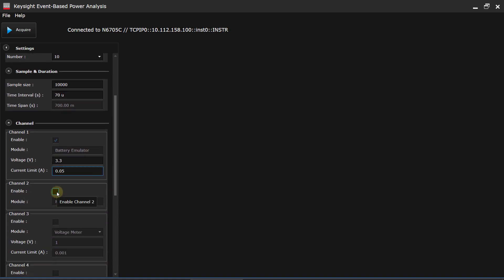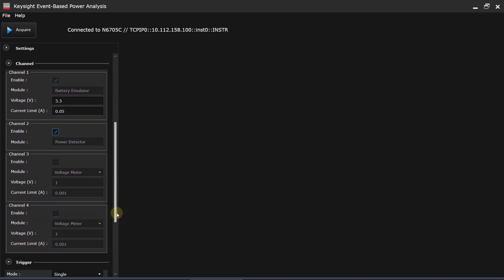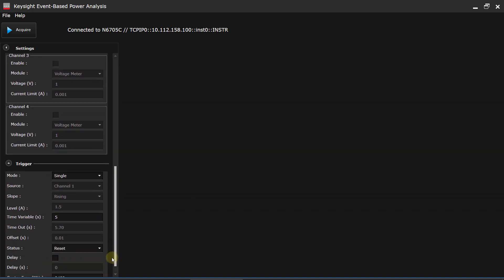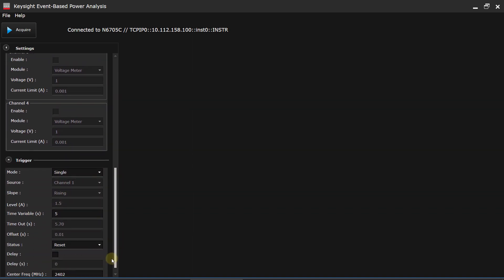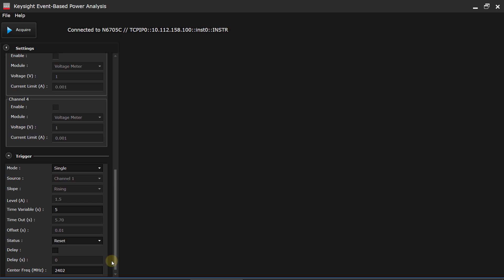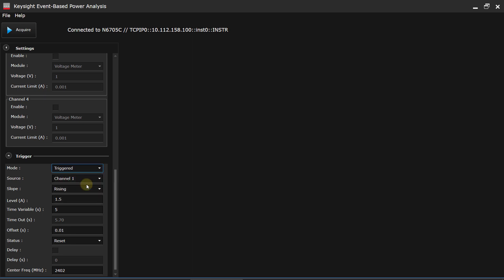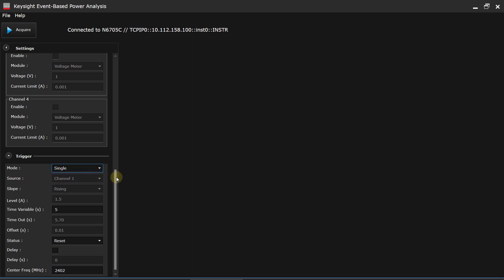I want to enable the RF power detector on channel 2. And that's really all I need to do. If I wanted to, I could go ahead and specify trigger parameters to trigger on a rising or falling edge. But in this case, we're just going to do a simple single trigger, which is a very easy thing to do.